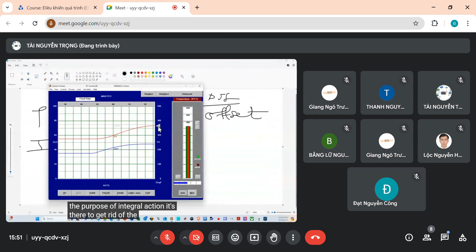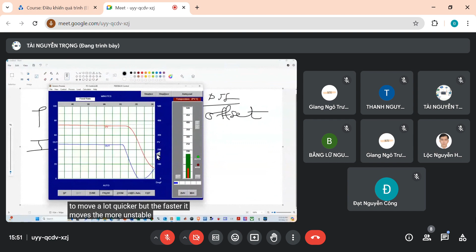I can make it faster if I want. Let's put in a value of maybe 0.16 - I'm going to make it faster. And now when I change the set point, it's going to move a lot quicker, but the faster it moves, the more unstable the process becomes. Imagine this is my level that I'm trying to control - you see how the level has gotten a little bit unstable. But it's going to sort itself out anyway.